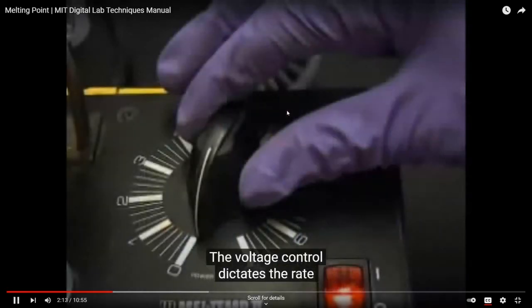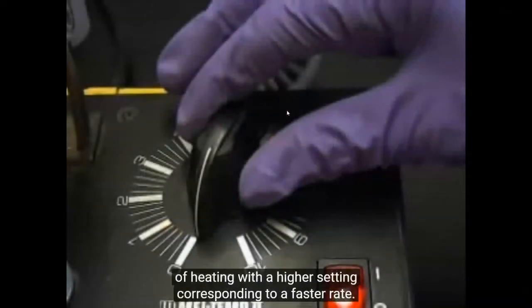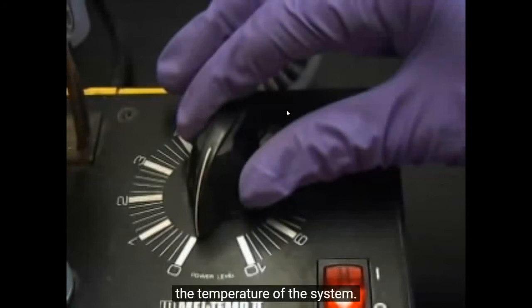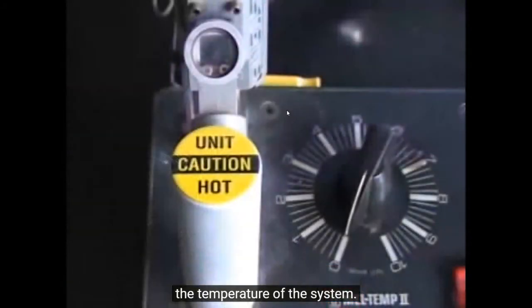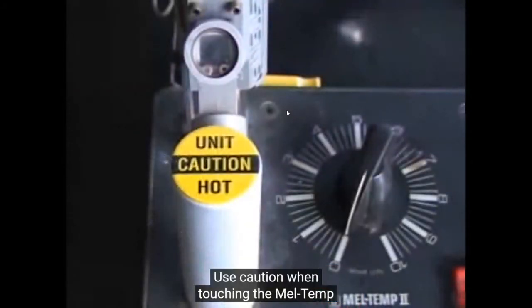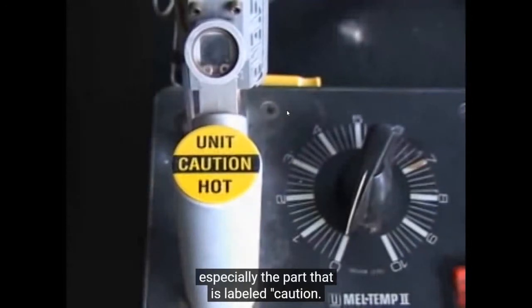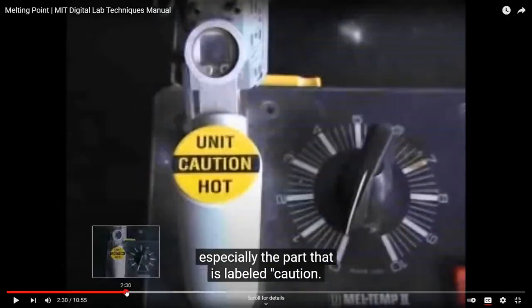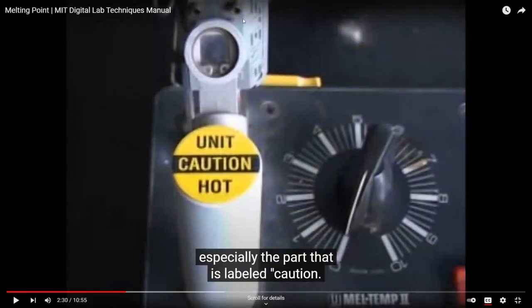The voltage control dictates the rate of heating with a higher setting corresponding to a faster rate. The voltage control does not control the temperature of the system. Use caution when touching the Mel-Temp and always assume that the apparatus is hot, especially the part that is labeled caution, unit hot. Okay, take a moment and imagine this in your head.